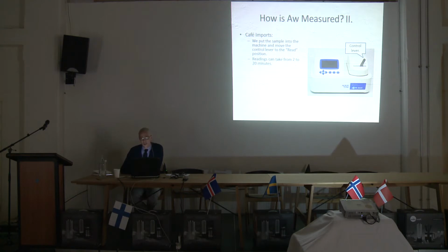Practically, readings can take a huge, there's wild variance in how long the readings take. It has to do with the temperature of the room, and the temperature of the coffee. If it sits in the sun for a moment, even if it's all sealed up and it gets warm, the machine will just start beeping and say the sample's too warm. If it's just under that, it won't complain, but it'll take 20 minutes to equalize the temperature and give you a reading. So if we're looking at roughly 100 coffees per week, and we're trying to get readings on all of them, when they start to take 20 minutes, that's a large time commitment to trying to collect this data. The machine is very, very sensitive.